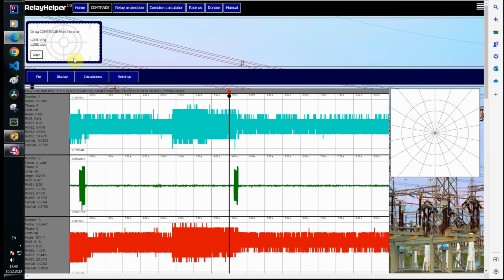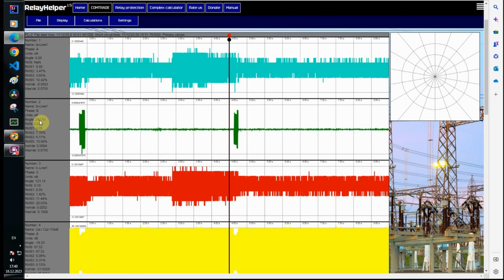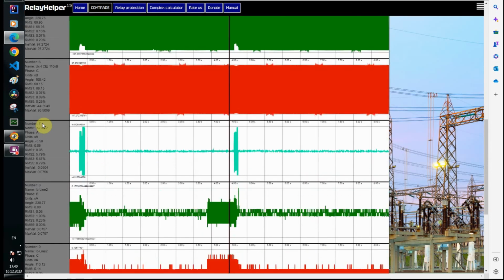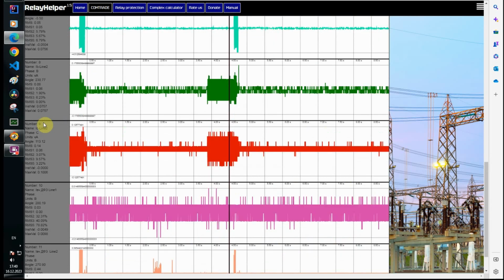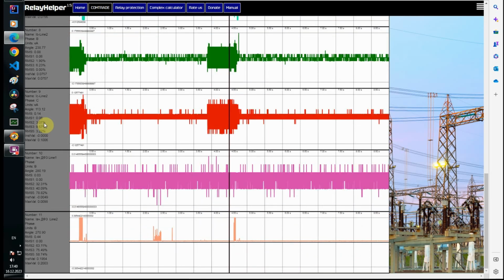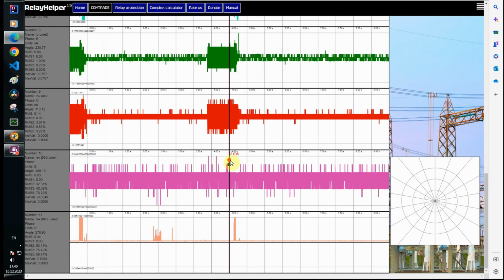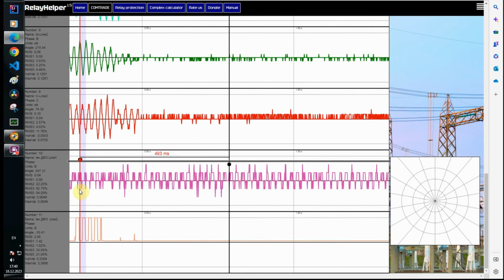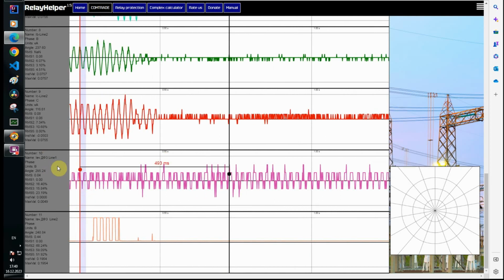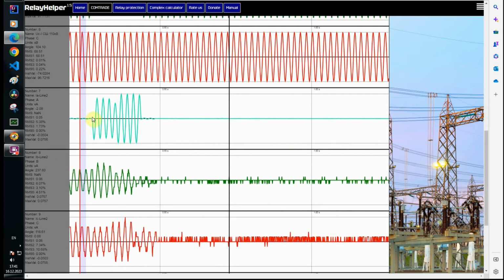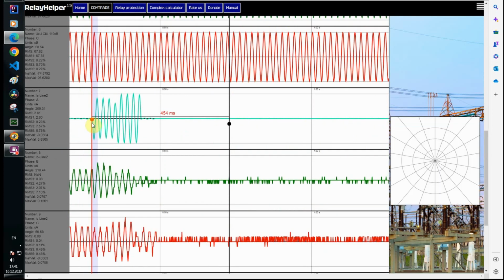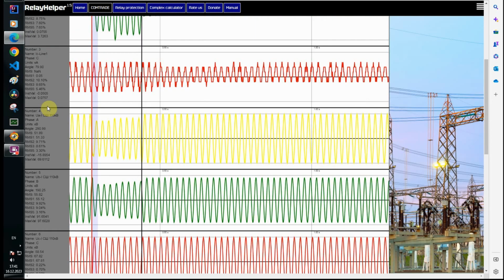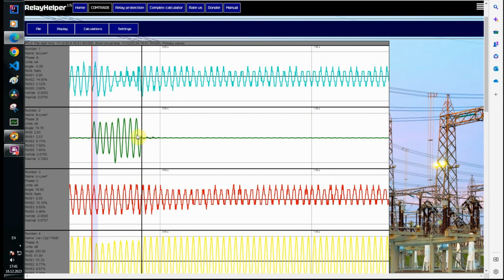Here is approximately the same for analog channels. But a high-frequency signal is also recorded along the lines. For the second line, there is a typical signal for the operation of phase differential protection for a short circuit on the protected object. On this side, the trip was longer, and this can be seen from the nature of the current. After the trip from substation A, the current increased. The longer trip time is due to the fact that at substation B there are older switches dating back to the times of the USSR.